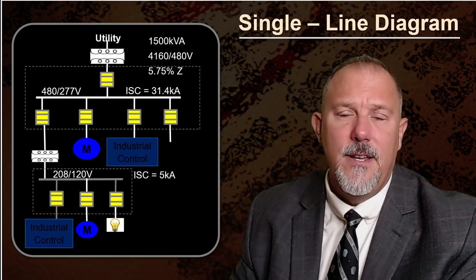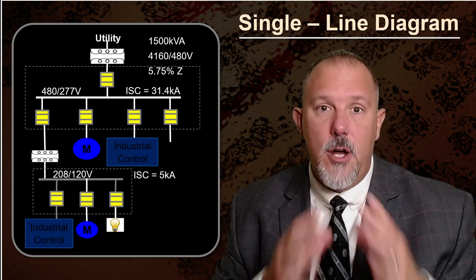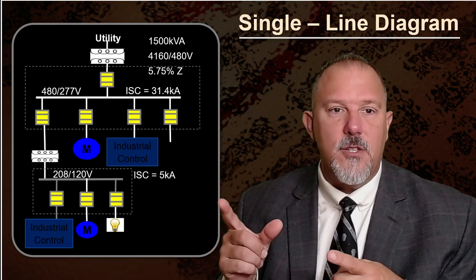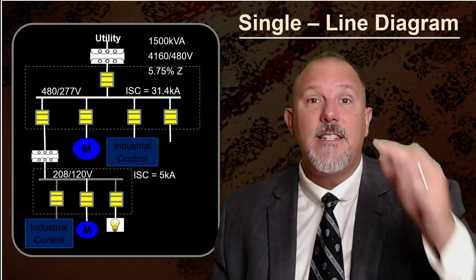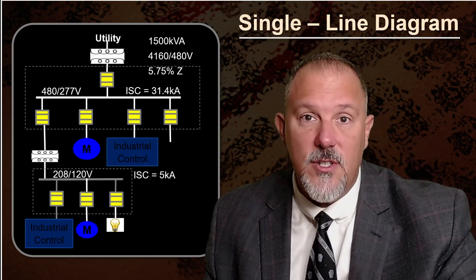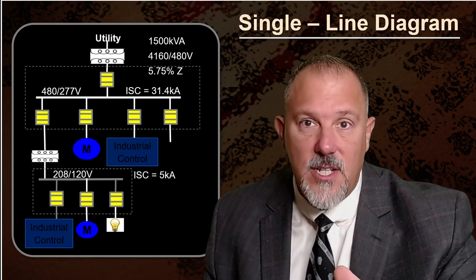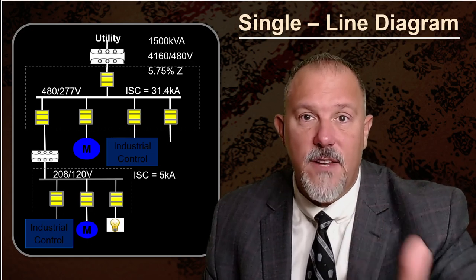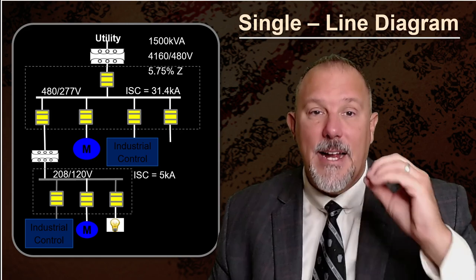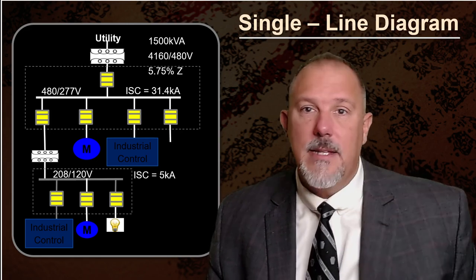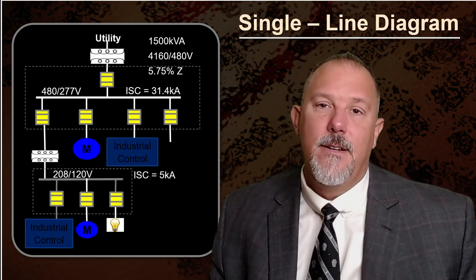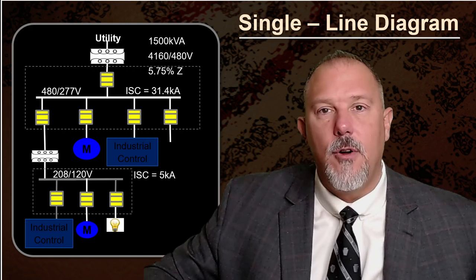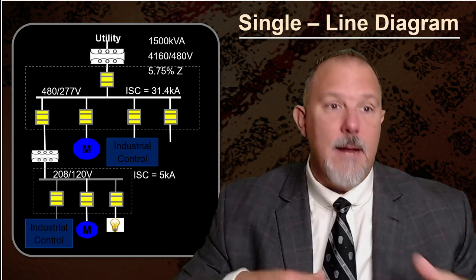Selective coordination. In a selectively coordinated system, if this one line diagram tells me, hey, I see a transfer switch, I see an emergency disconnect or emergency generator, I know I have an emergency system per Article 700, 701, 708, I know I'm going to be selectively coordinating that system. I'm going to have my severity be high with regard to arc flash. And then I'm looking for solutions.